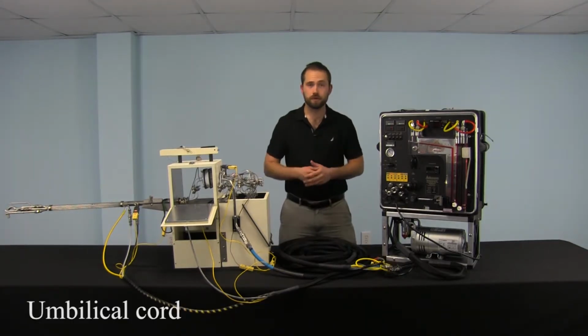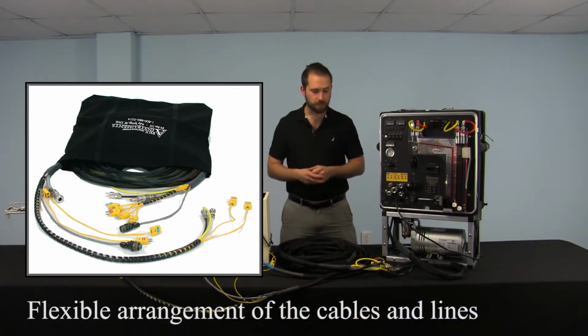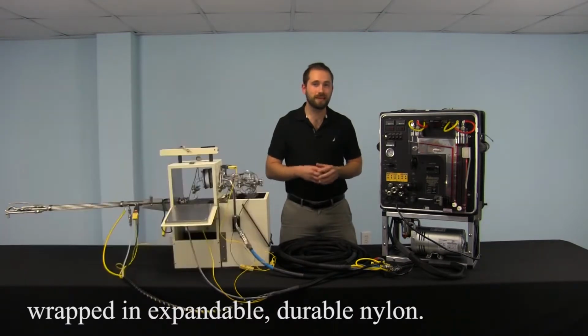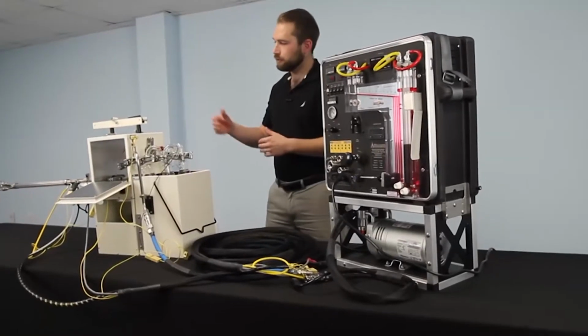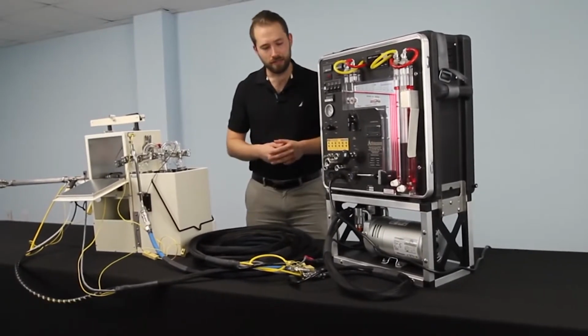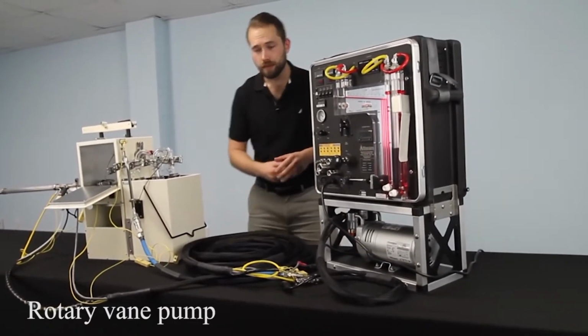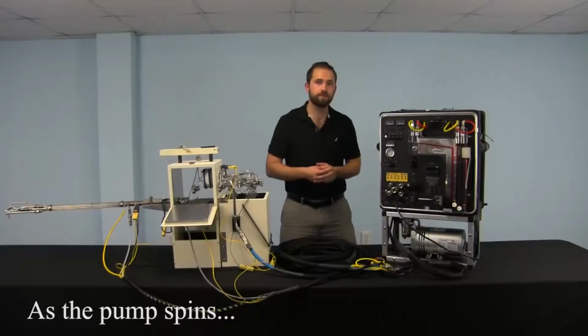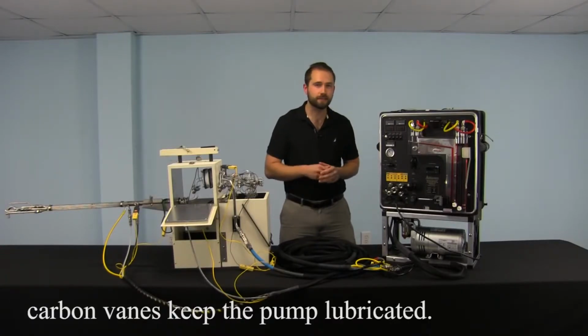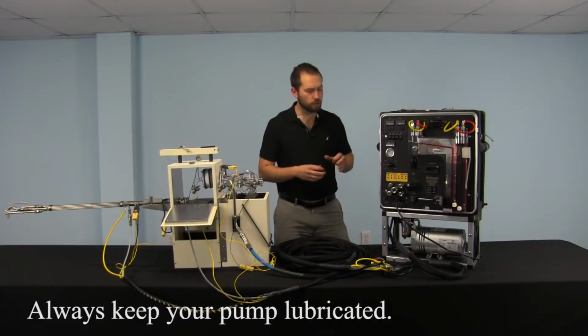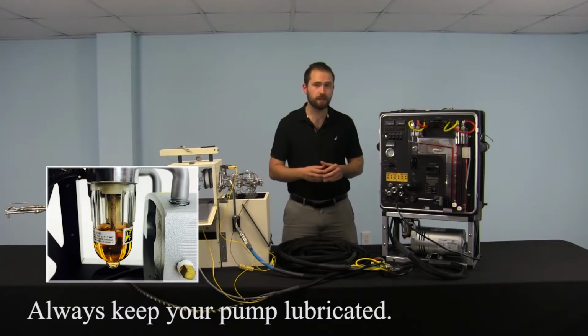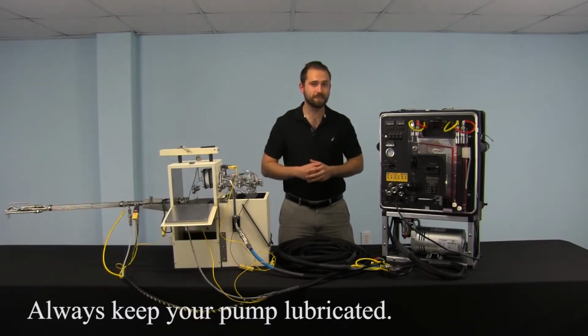Next, we have the umbilical cord, which is a flexible arrangement of all the cables and lines wrapped in expandable, durable nylon. The pump that we use to pull the air from the source is a rotary vane pump. And as this section right here spins, it uses little carbon vanes to keep itself lubricated. You always want to make sure to keep your pump lubricated, otherwise it will eventually seize.